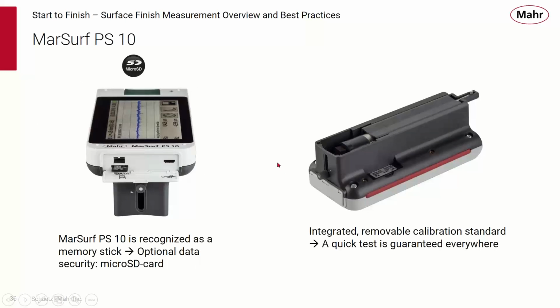All the measurements you make are put onto a memory stick, the micro SD card, and you can plug that into your PC and view those results. We have this integrated calibration standard, which is unique. You can pull it out and make a quick test to get guaranteed results anywhere.